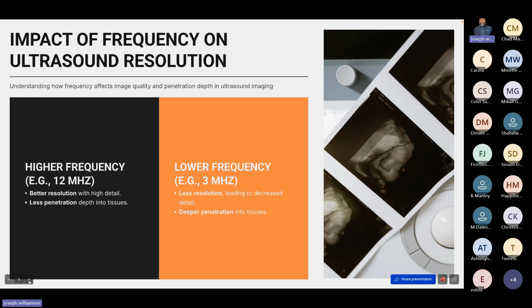Does everybody understand that concept? That is a very, very difficult concept for some people to grasp. High frequency, better resolution, high detail, but less penetration. Low frequency, less resolution, not enough detail, but I can penetrate really, really a lot. Okay, so try to remember that. This is a very important slide for you to remember. When you get these slides, try to remember number 6, high frequency and low frequency. We need to understand how frequency affects the image quality and the penetration depth.